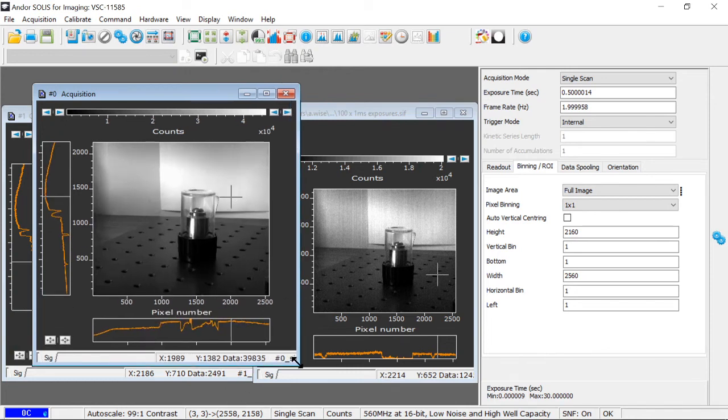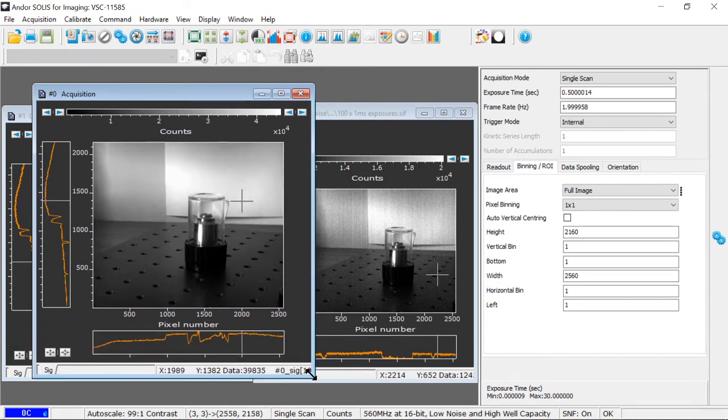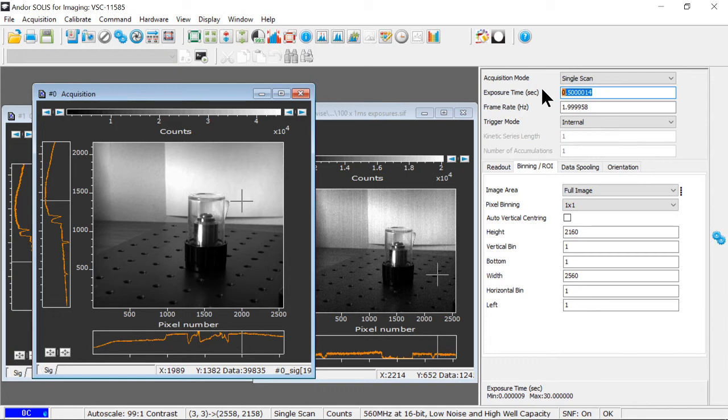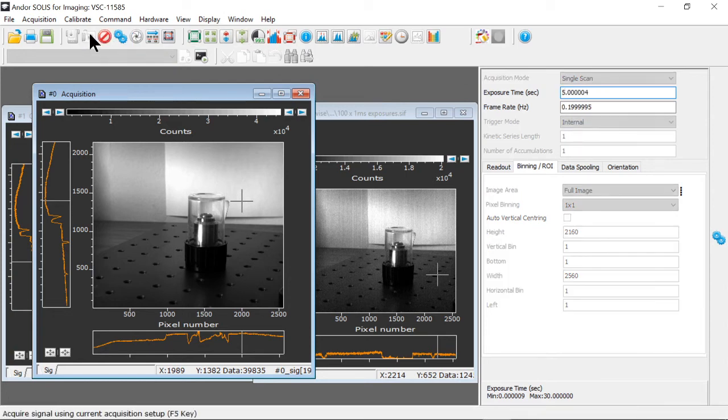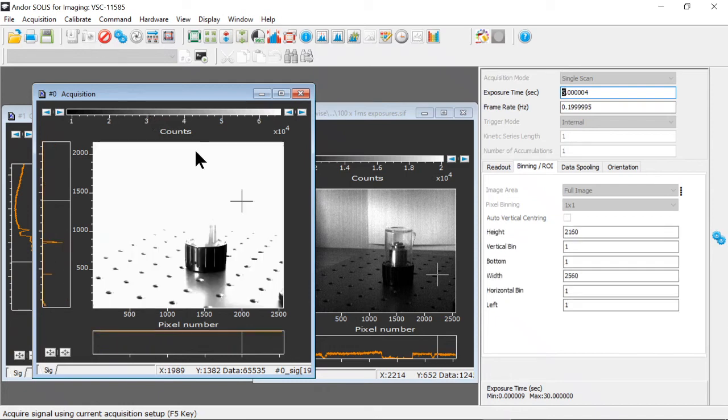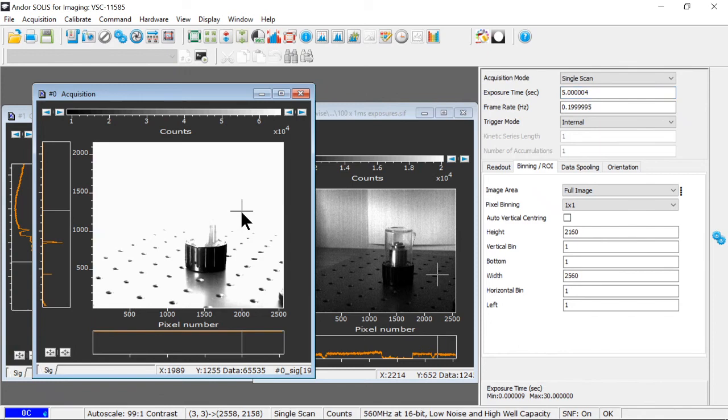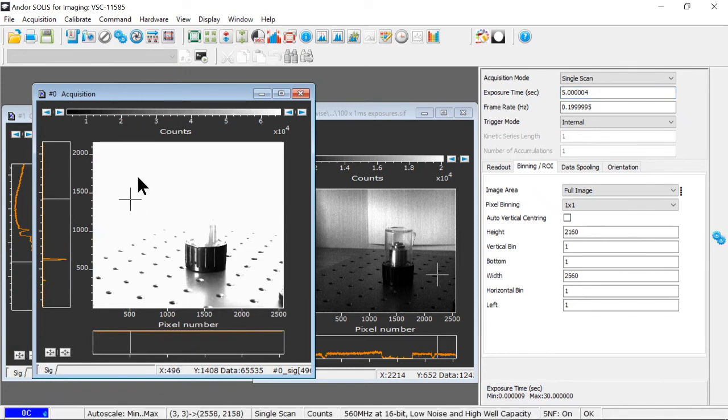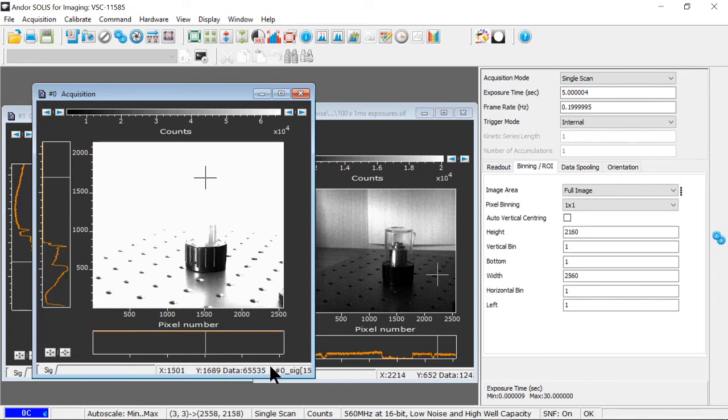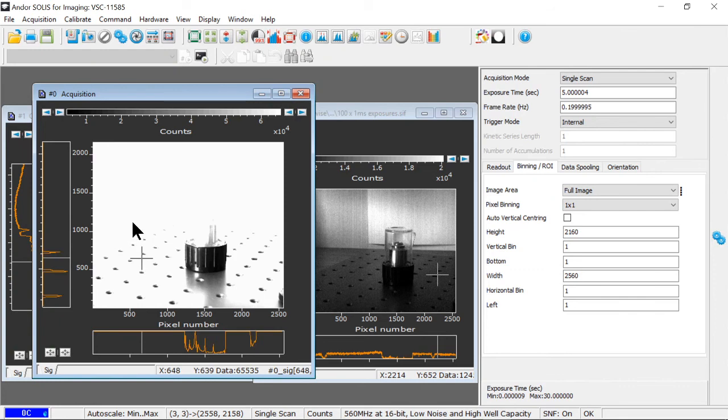If I wanted more signal out of this image, I could increase the exposure, say, by a factor of 10. And keep in mind I'm starting at 500 milliseconds. So I go to five seconds, acquire an image. And this will take a few seconds. And I've saturated the ADC. So you can see that I'm losing a lot of information. And I'm saturated at 65,535 with a 16-bit ADC here. So I can't recover that contrast that I've lost.